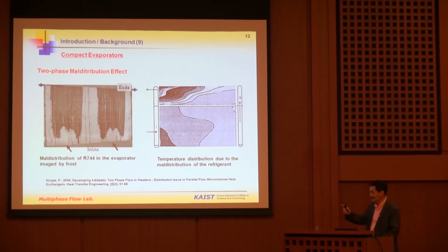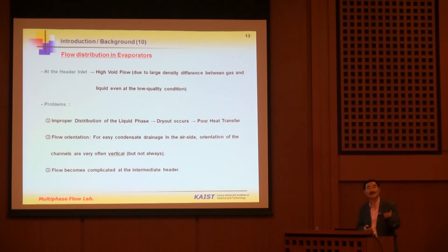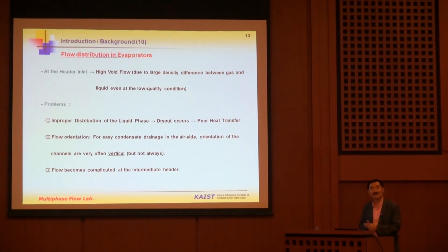In the case of the evaporator, at the header inlet from the expansion valve, we have two-phase mixture coming out with low quality. The evaporator is in a low-pressure condition, which means a large difference between liquid and gas in density and viscosity — i.e., high void fraction — and that causes large flow maldistribution. If there is improper distribution of the liquid phase, dry-out occurs in some portions of the heat exchanger, causing poor heat transfer.